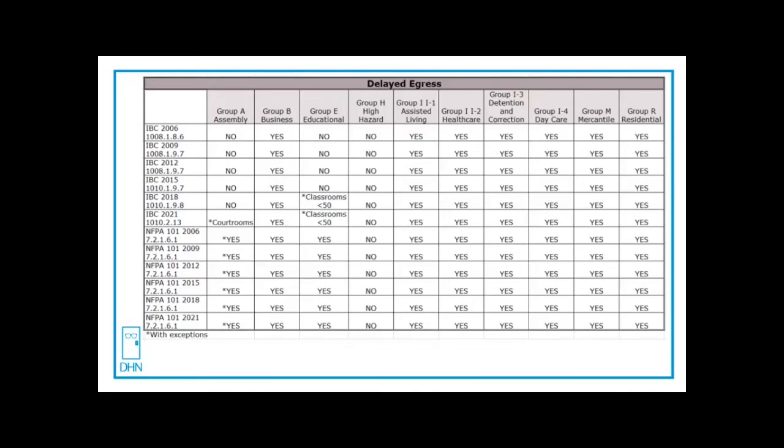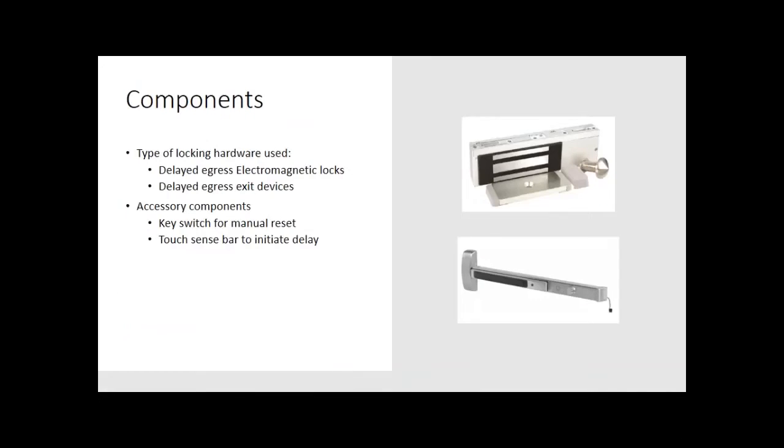The most common components for delayed egress would either be a self-contained electromagnetic lock or a self-contained exit device that has all of the components, including the reset. If you are using the mag lock version, you probably need a key switch for manual reset. It needs to be done at the door.